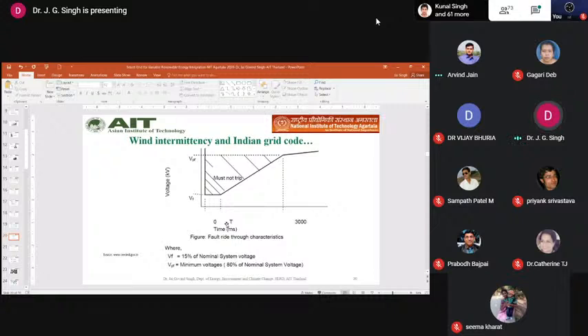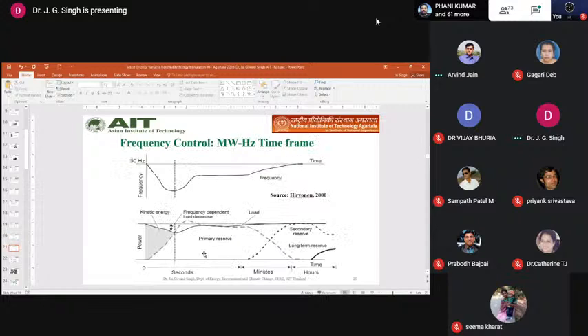For the Indian system, this is the grid code. You can see it goes to 15% minimum at the fault point and has to restore to 80% before 3000 milliseconds. This is the period where solar and wind sources should not be disconnected if there's a fault. But below this curve, they are free to disconnect from the system if the fault persists longer.